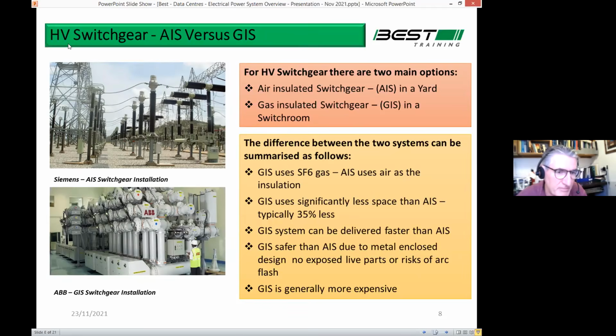So the power comes in on the pylons, drops down, and you can see all these insulators, and things like current transformers, circuit breakers, disconnect switches, and so on. So it takes up a vast amount of space, this type of switchgear arrangement. That's what we call air insulated, or AIS for short.